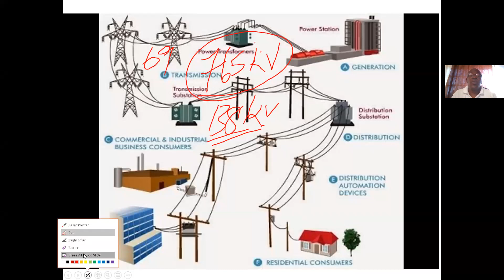So in terms of voltage levels, we have high voltage, which in our case is 69 and 138, and extra high voltage, which is 765. In some other jurisdictions, for example the UK, they operate at 400 kilovolts at the transmission level. But at those voltages, there are other things they have put in place which we will not speak to as far as power systems is concerned - we leave that for when we talk about protection and other attendant issues. So those are the transmission voltages we operate at.